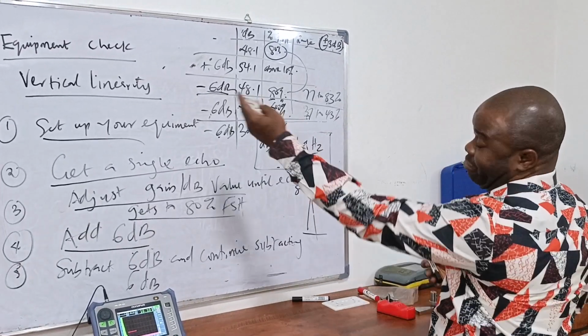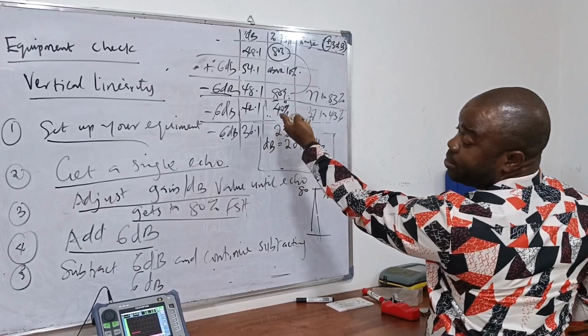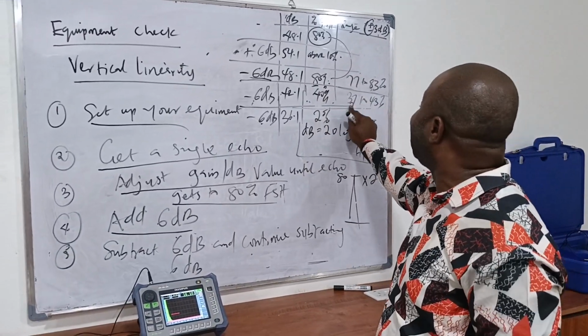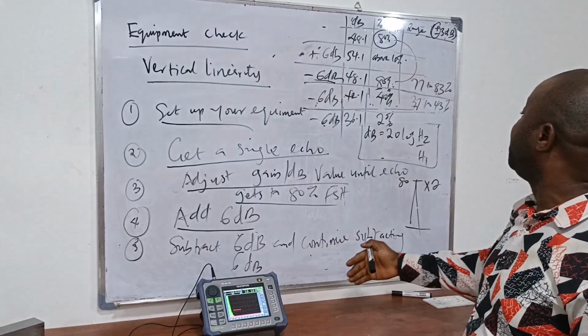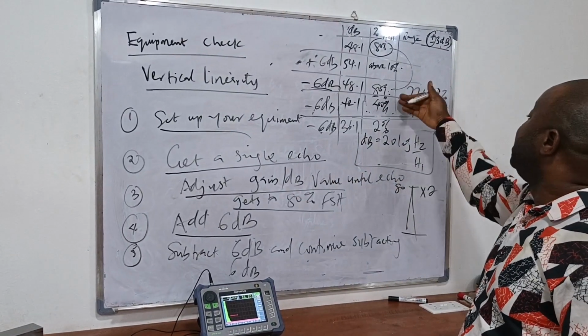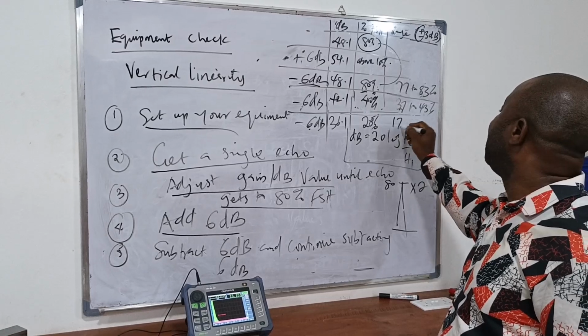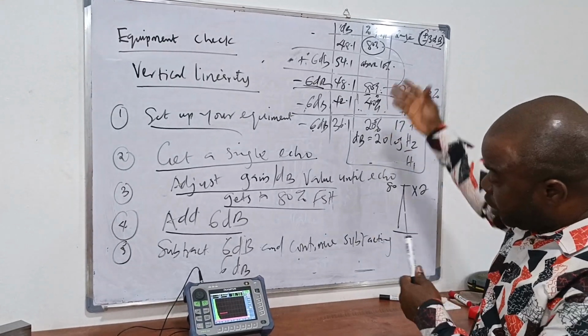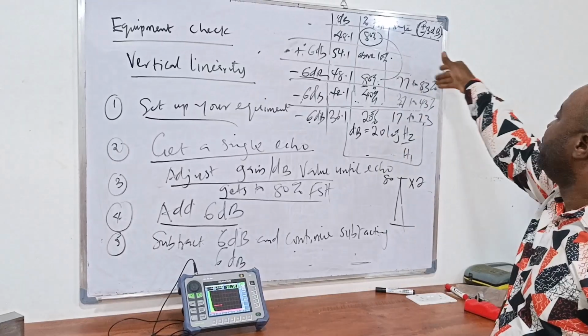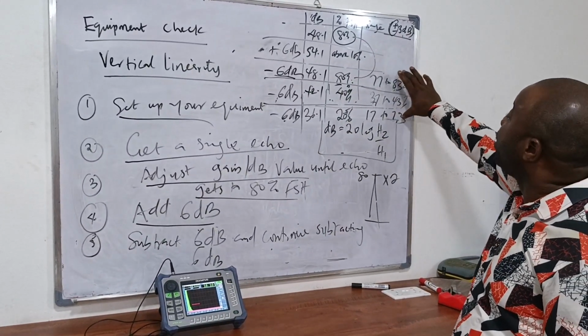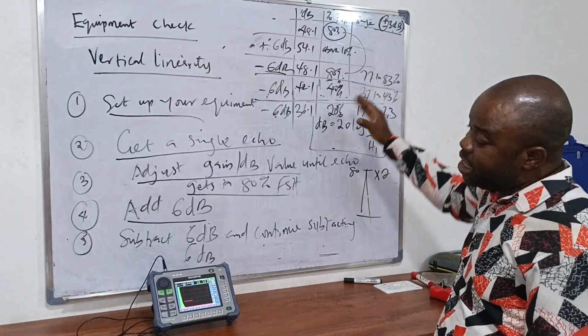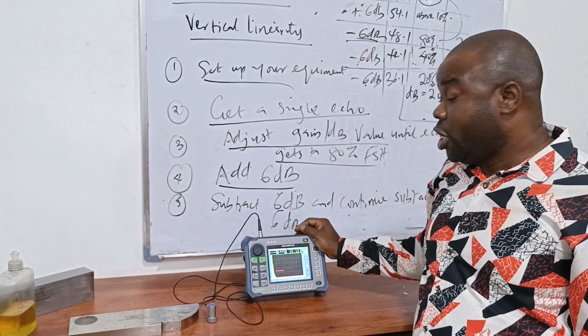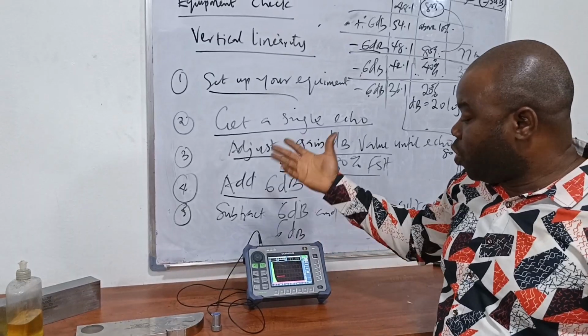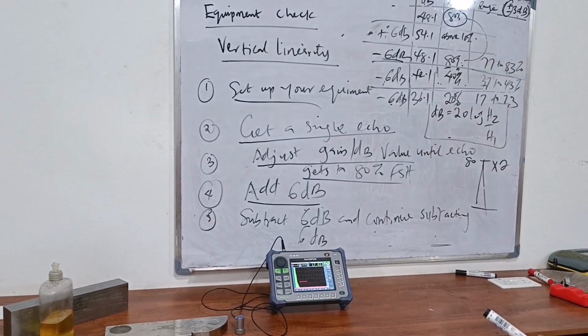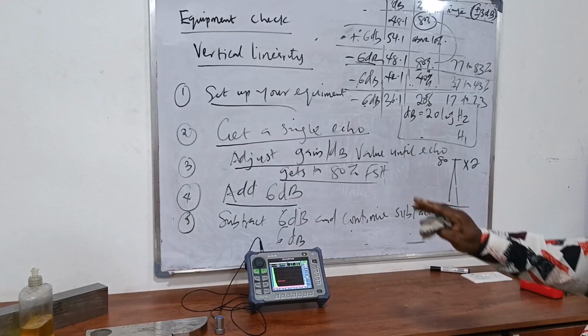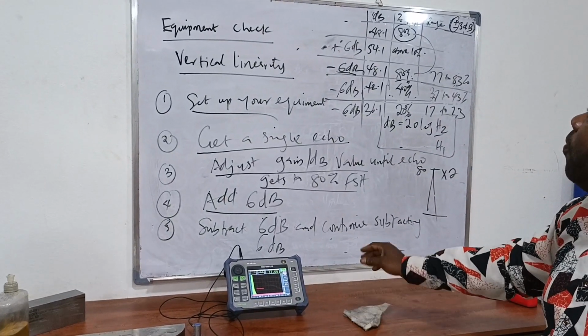You don't necessarily need to have a 40% full screen height. But if you are getting between 37 to 43, it means that your vertical linearity is okay for the equipment. The same with 20%, which means 17 to 23. So you record these values and check for this, and if there is any error, if the values are going outside of this range, it means that your vertical linearity of your machine is not good. So you have to send it for calibration or reset, as the case may be. So that is just a summary of how you do your vertical linearity.